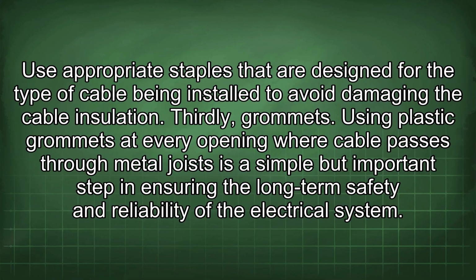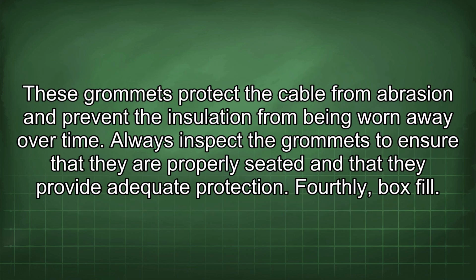Thirdly, grommets. Using plastic grommets at every opening where cable passes through metal joists is a simple but important step in ensuring the long-term safety and reliability of the electrical system. These grommets protect the cable from abrasion and prevent the insulation from being worn away over time. Always inspect the grommets to ensure that they are properly seated and that they provide adequate protection.